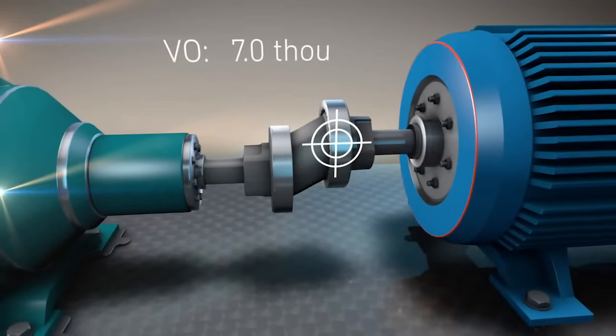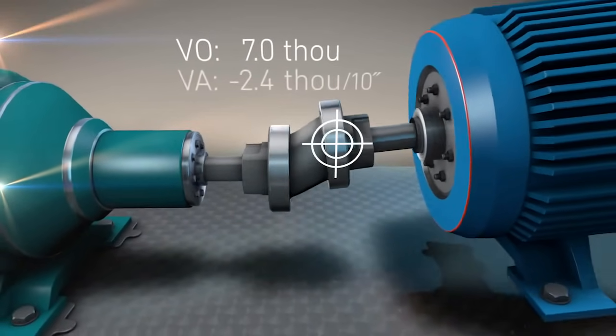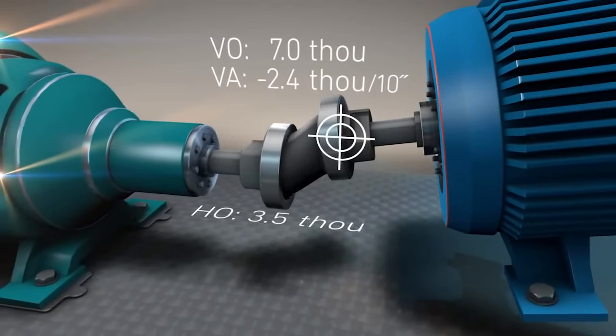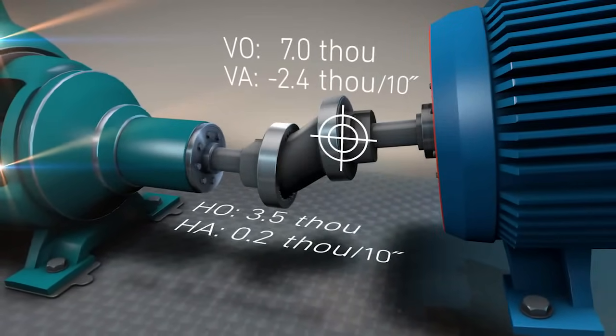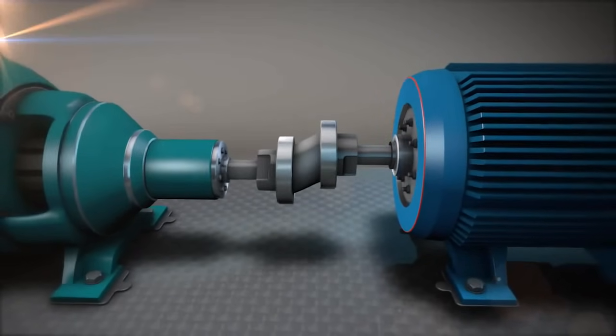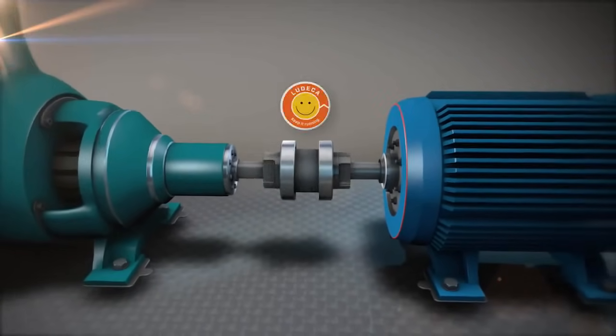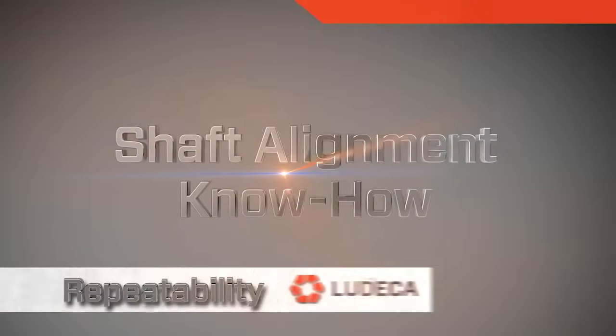Once you know how the machines move with respect to each other, it is very important to input the target values in your laser shaft alignment system if it features this capability. It will then calculate where machines should be positioned when cold and stopped to get correct alignment when they are running.